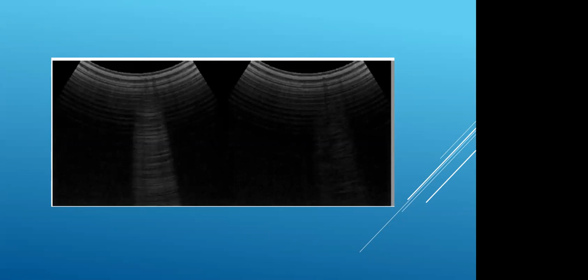And everybody can actually quickly use that as a QA system. Or what you could do is buy a commercial phantom, which does quite a lot of the measurements from uniformity to dead zone assessment. But you are probably looking at an investment of around $3,000 US, which I believe, for a quality institution, should not be much.